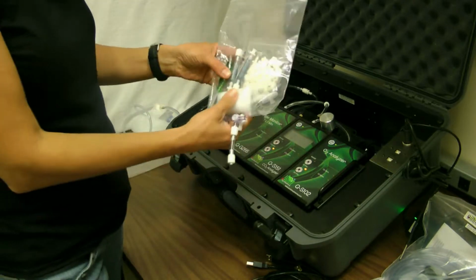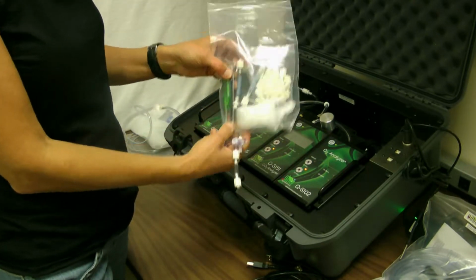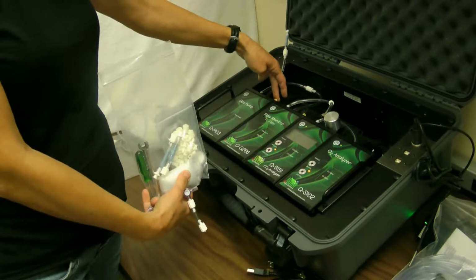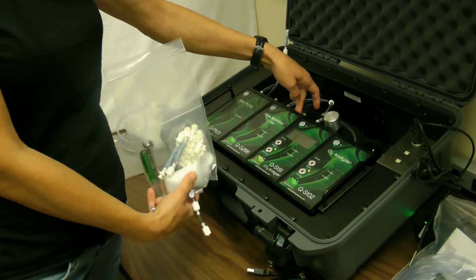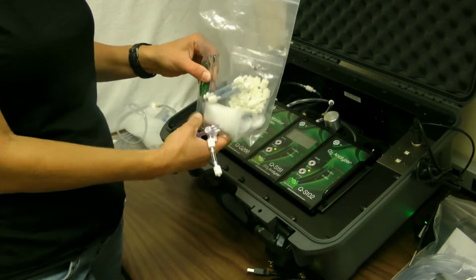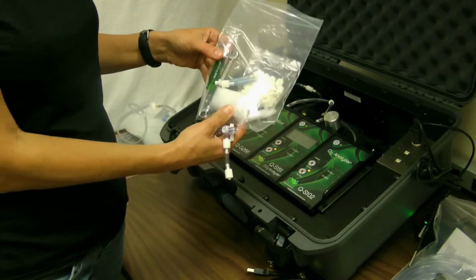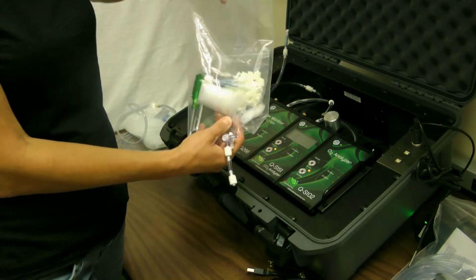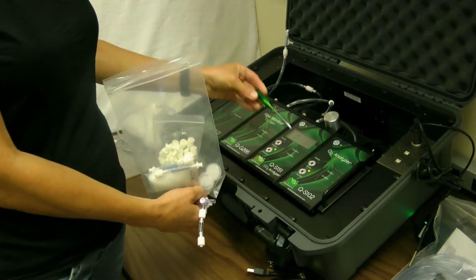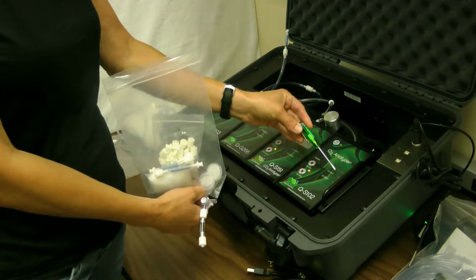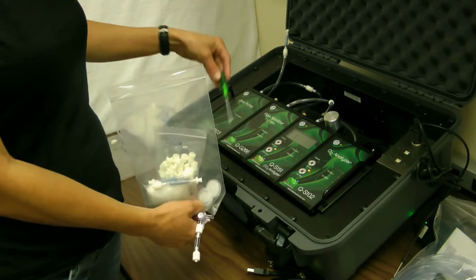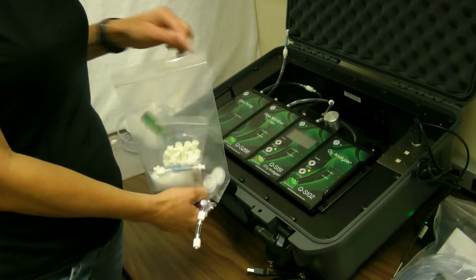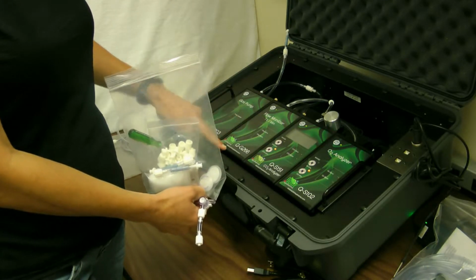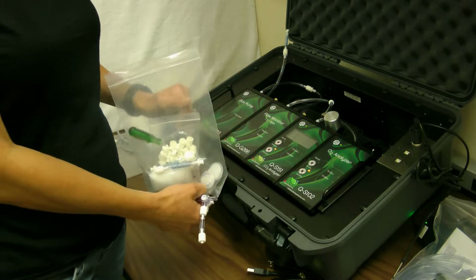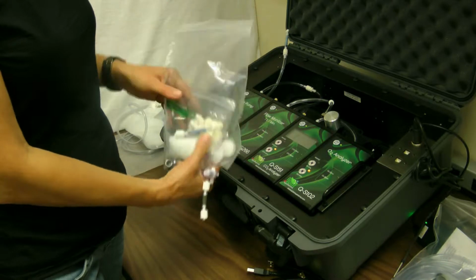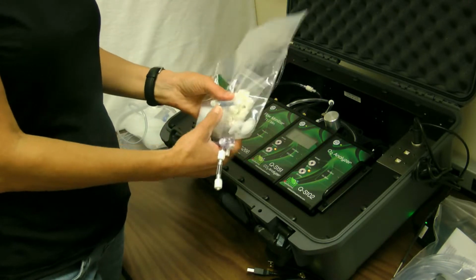And in the other bag here, we have a little wrench that you need to adjust needle valves on the back of the flow monitor and the gas pump. There is a locking nut that has to be tightened after you've adjusted your flow rates, and you use this wrench for that. And there's a small screwdriver that is used during calibration for adjusting the CO2 zero, CO2 span, oxygen zero, oxygen span, and it can also be used to adjust zero flow. And that's explained in the manual. Flow span should not be used unless you have a flow standard. And there's some extra connectors as well.